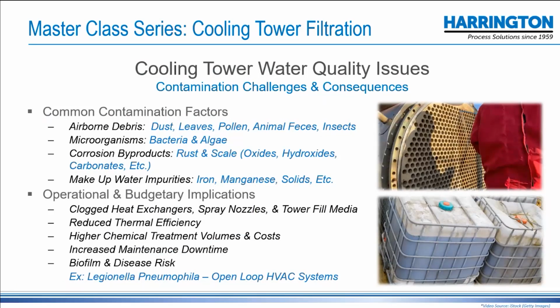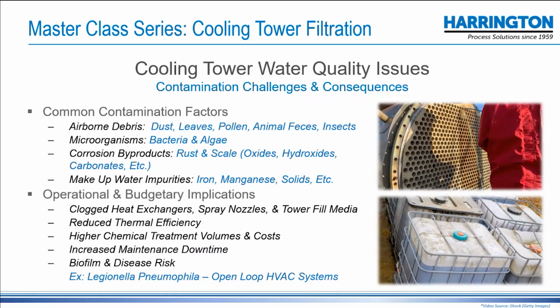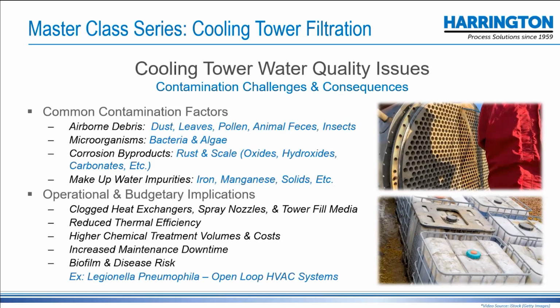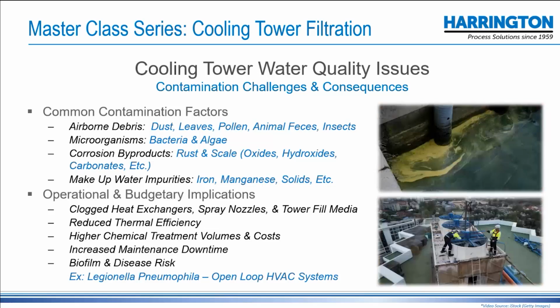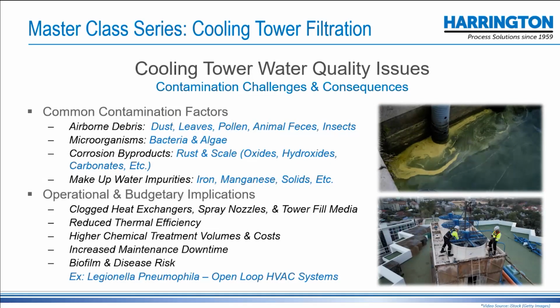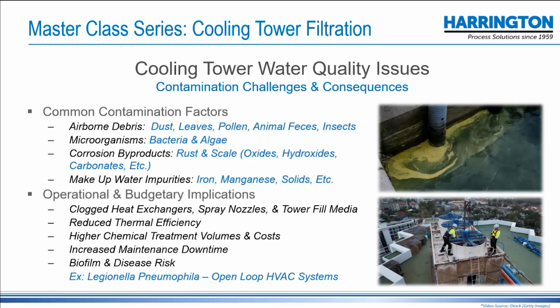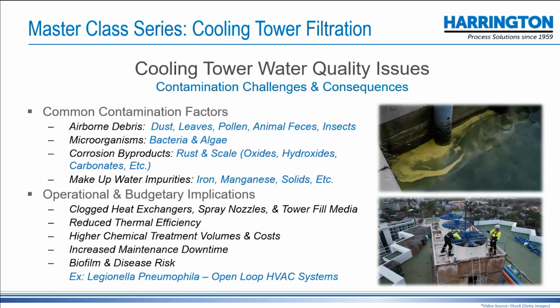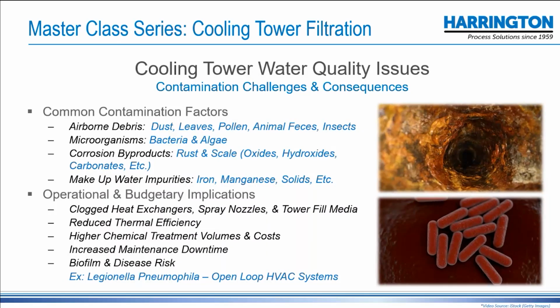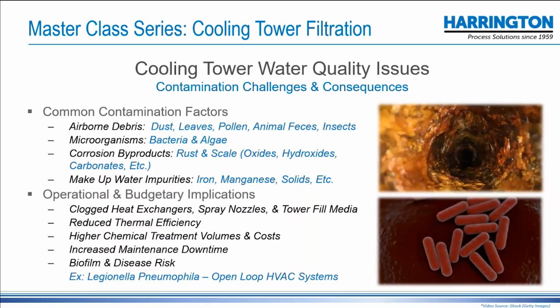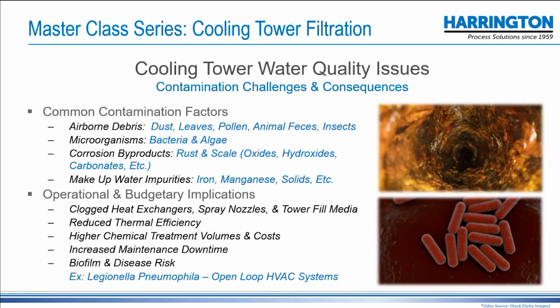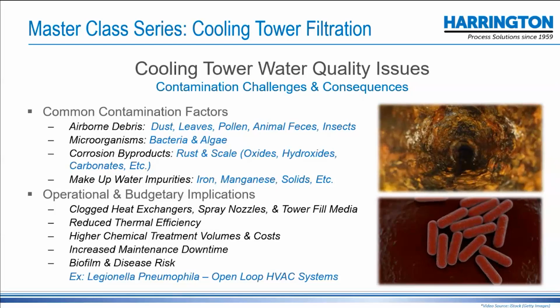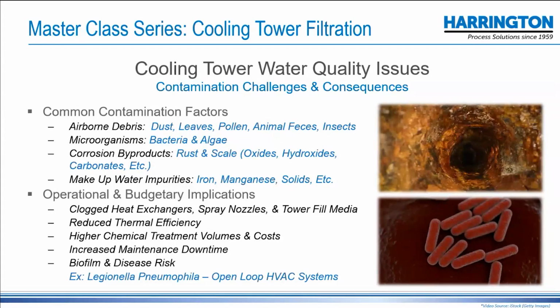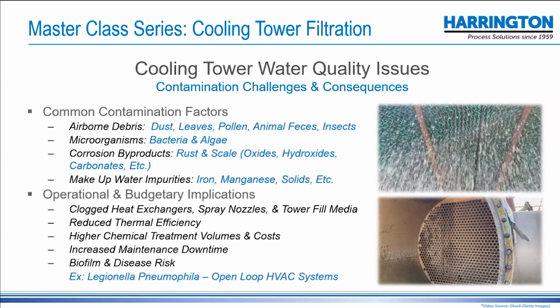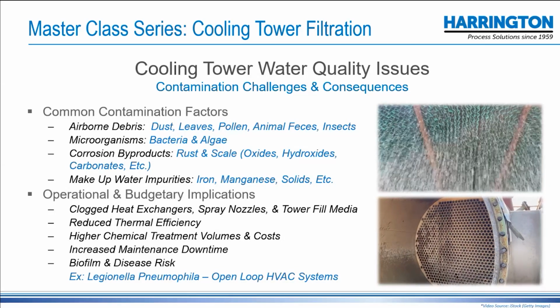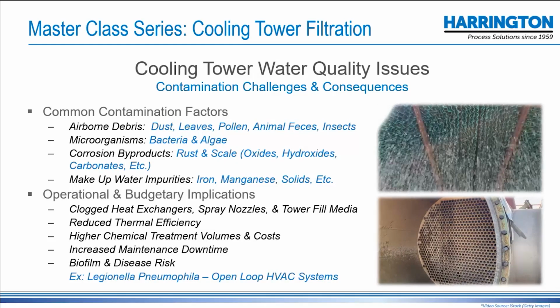Common water quality issues, I described some of them: dust, pollen, leaves, animal feces, or even animals themselves. Certainly insects, bird droppings. You can get microorganisms, bacteria, and algae into a system. One of the major concerns is corrosion byproducts, rust, scale, oxides and hydroxides that can gum up pipe and cause blockages within the cooling tower. So the implications dollar-wise is a clogged heat exchanger is something you have to clean out, and it could fail over time. Spray nozzles, as I described earlier, and the fill media of the water tower, the upper right image, you get reduced thermal efficiency.